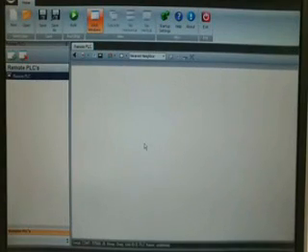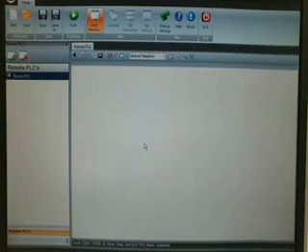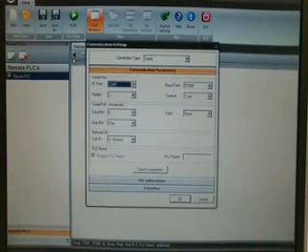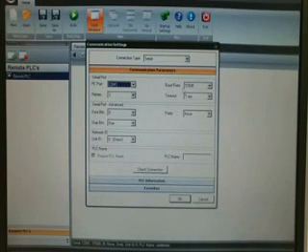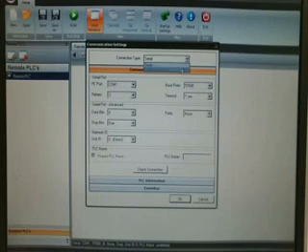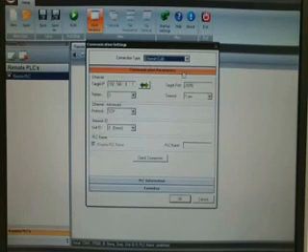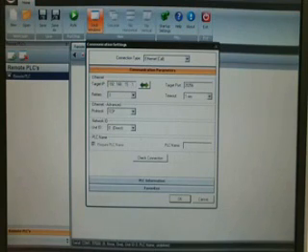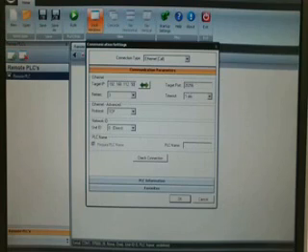Okay, the next step is to configure the remote operator to communicate to the ethernet port on the PLC. So the first thing we're going to do is we're going to go ahead and hit the communication settings icon, which brings up the settings box. And notice here it's set for serial. We're going to change that to ethernet. And we'll type in the PLC's IP address. It was 192.168.112.50.